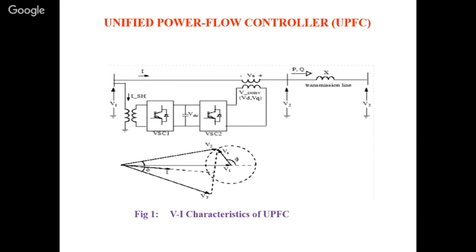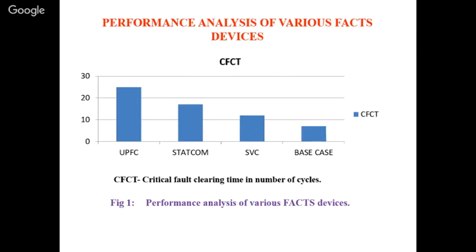The VSC takes real or active/reactive power from here, feeds it to the Vdc, and gives it to this part. The main advantage is dynamic control of voltage — it can move in both directions. To really understand this concept, you should study the phase-shift transformer — UPFC is essentially a modern version of the phase-shift transformer. If you understand the phase-shift transformer, you can understand UPFC also.